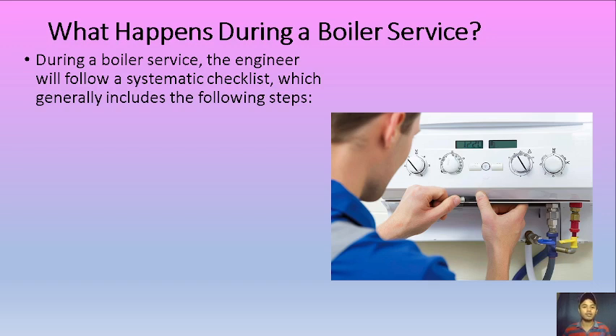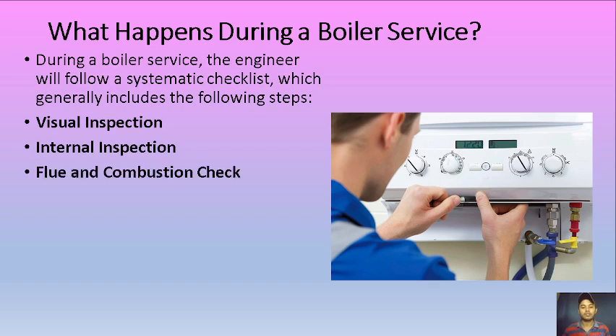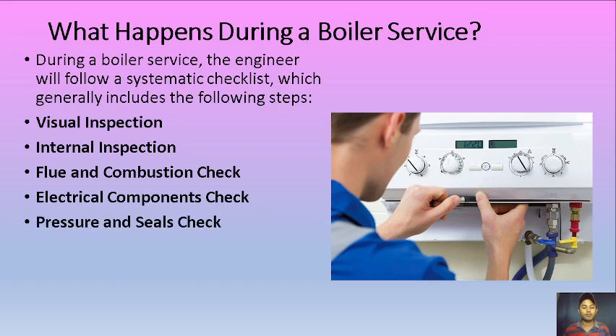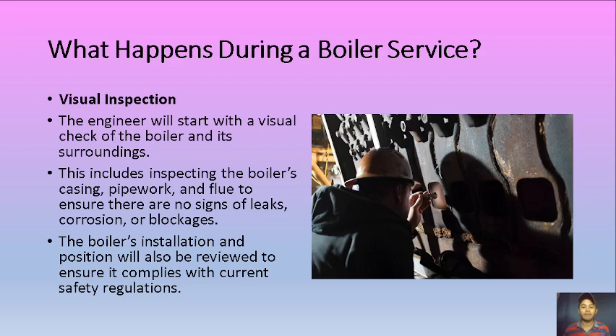Okay, so what happens during a boiler service? During a boiler service, the engineer will follow a systematic checklist, which generally includes the following steps. Visual inspection. So you will have to check visually whether there is anything unusual on all your equipment. We have internal inspection, we have flue and combustion check, we have electrical components check, we have pressure and seals check, and cleaning and operational check. So these are the usual checkings that we have to do every day. So what happens during a boiler service?